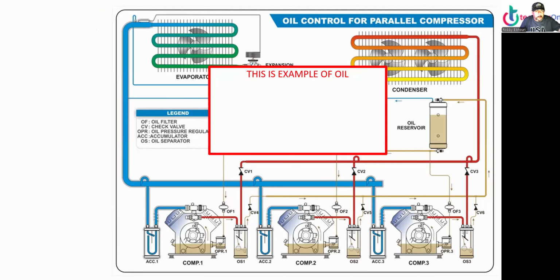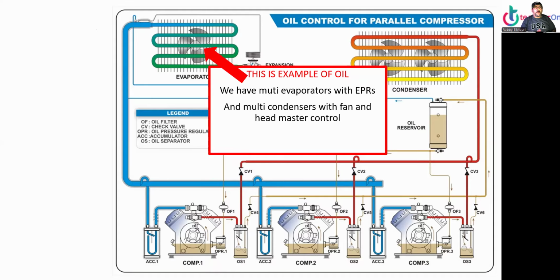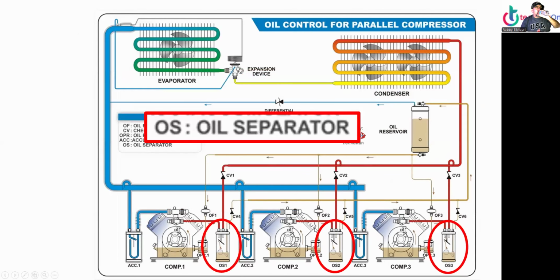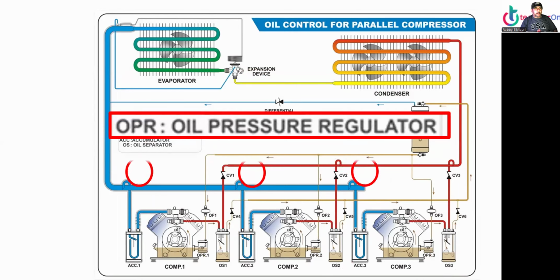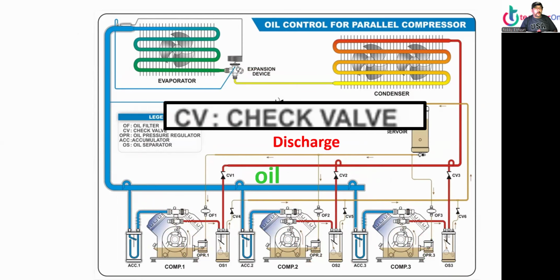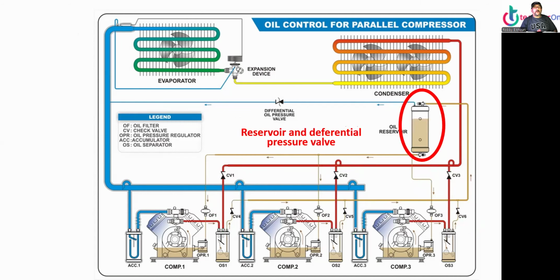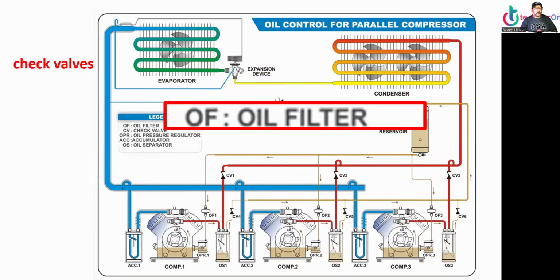Oil control for parallel compressors. This is an example. We have multiple evaporators with EPRs, and multiple condensers with fan control and headmaster also. Just imagine 3 big compressors for just 2 small condensers, and also liquid receivers and other good stuff, a suction filter. All right, first we have the oil separators there at the bottom, and oil pressure regulators, 1, 2. Check valves: we have the refrigerant check valve, the oil check valve, the discharge check valve, the oil reservoir and differential pressure, and oil filters.